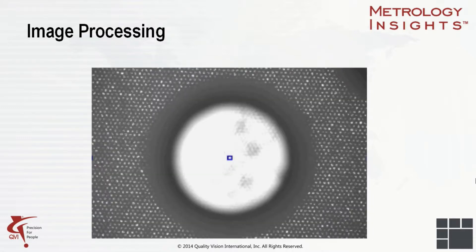In this scene, we see a frequent problem in optical measurement. The surface of this metal part is very shiny — so shiny that all the light reflects off it and we can't focus it sharply. A similar problem occurs when we try to focus on translucent materials; the light passes through the surface so we can't see it clearly. In order to focus on areas like these that have no natural contrast, we can project an image of artificial contrast onto the surface to give it the appearance of texture. The checkerboard grid pattern is focused at exactly the focal length of the optics. The grid appears sharply focused when the part surface is in focus.